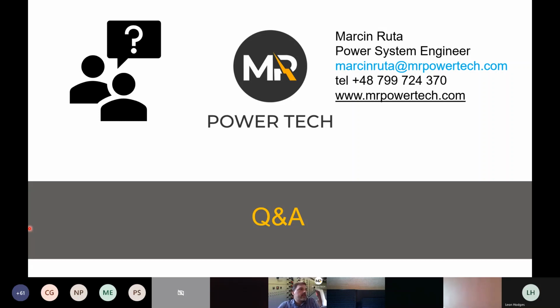So Chris asked: IEC 60909 and IEC 61363 cover short circuit fault calculation but do not extend to arc flash incident energy calculation, hence we typically revert back to IEEE. Do you know if there is an IEC standard guidance in development to provide more IEC-focused guidance for arc flash incident energy calculation? So yes, there is.